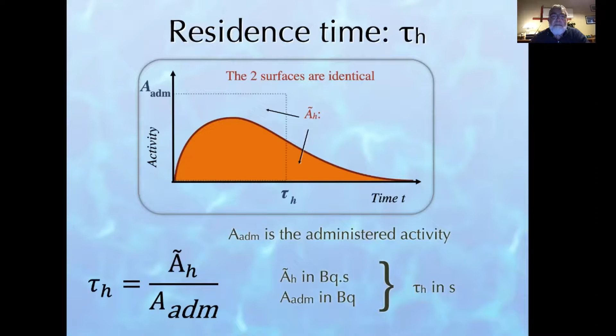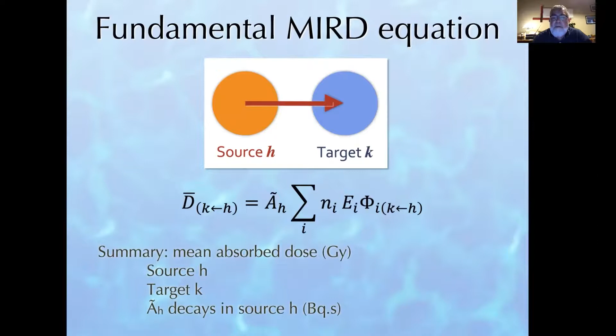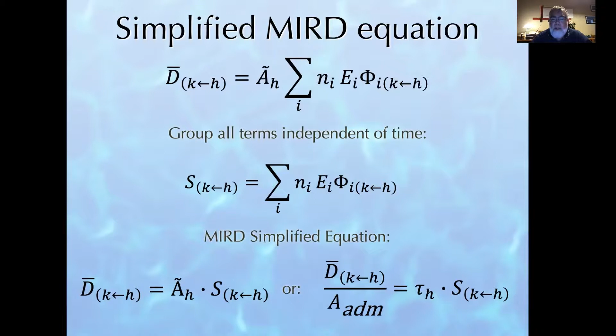So we end up with a fundamental MIRD equation that says that the absorbed dose in the target K from source H is the accumulated activity in the source multiplied by the sum for all the radiation types I of the probability of emission, the energy, and the specific absorbed fraction. In fact, because many factors do not vary as a function of time, we can group them, and we introduce the S value, which is the sum for all the particle types I of Ni, Ei, Phi. The S value allows us to present the simplified MIRD equation, as is here at the bottom left: the absorbed dose in the target from the source per activity administered to the patient is the residence time multiplied by the S value.